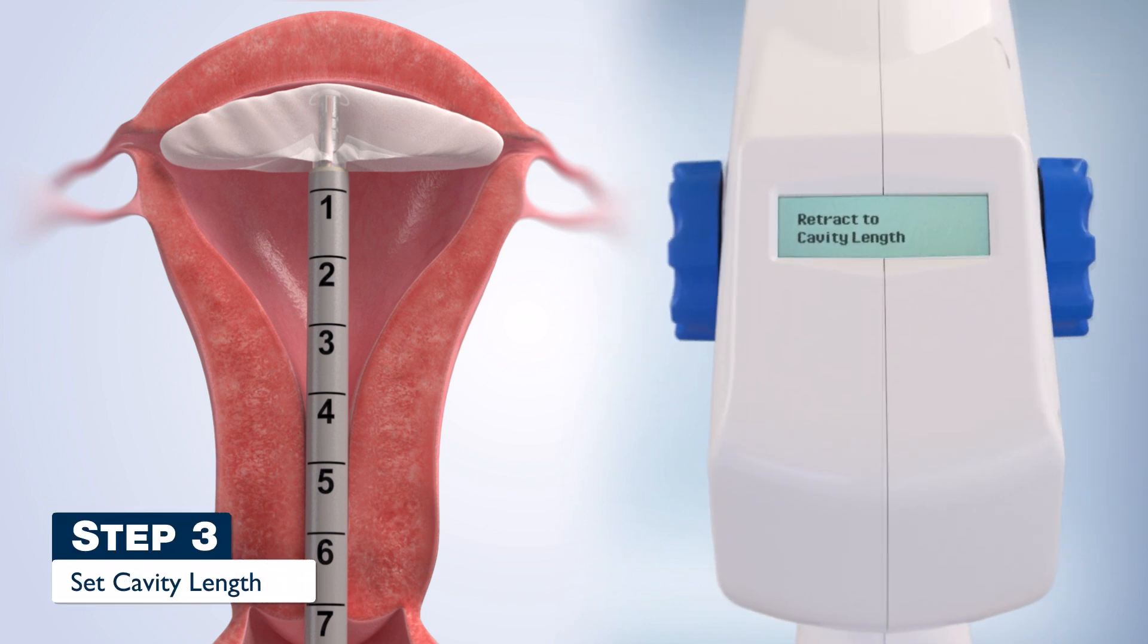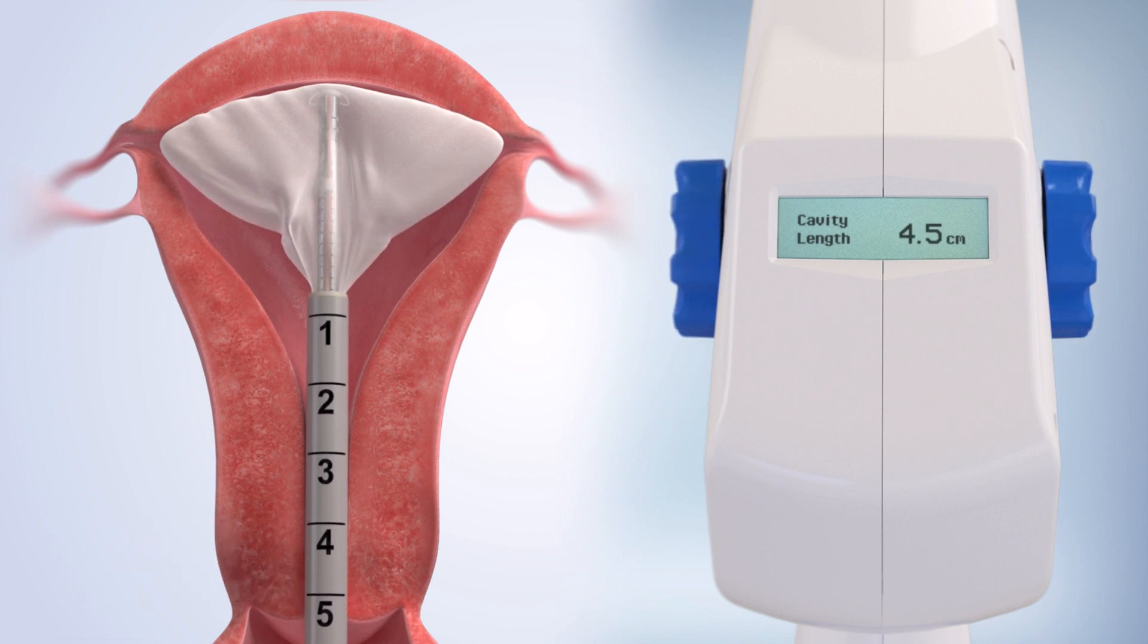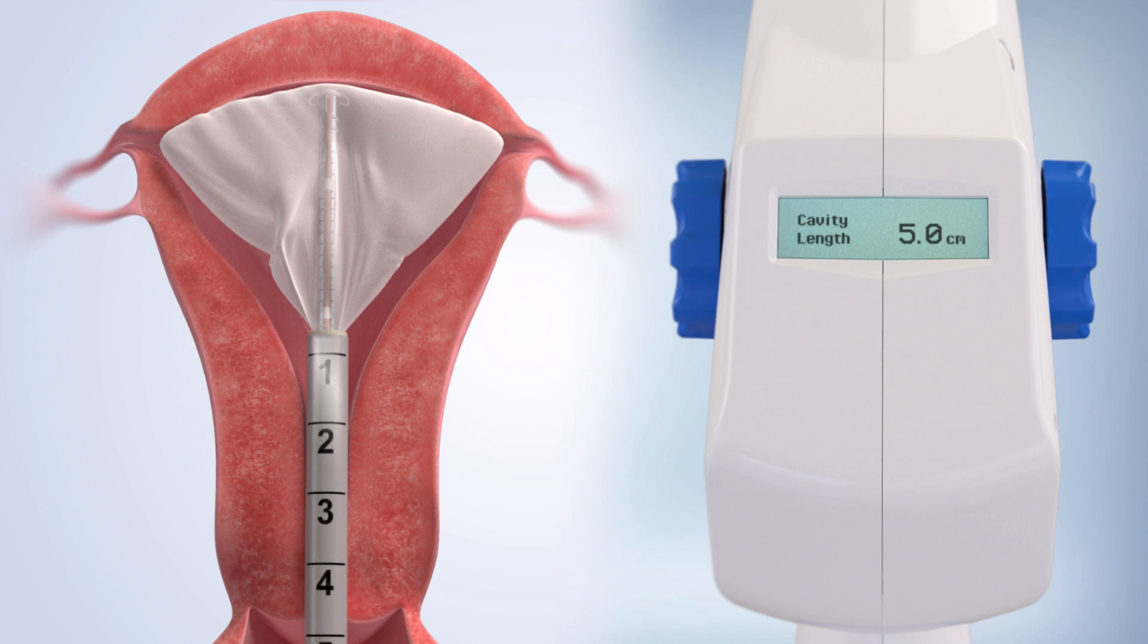Step 3. Turn the sheath retraction knob until the calculated uterine cavity length is displayed on the LCD screen. The sheath is designed to protect the cervix and adjacent tissue. Gently reconfirm that the probe tip is at the fundus.